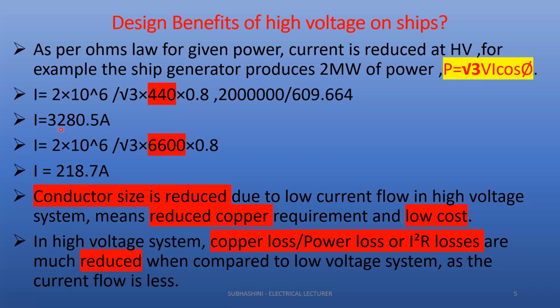So from 3300, the current value has come down to 220. So we can see the change. We can see the difference between 3300 and 220. So this many times the current is getting reduced since we raised the voltage from 440 to 6600. But the power is the same. The power we use here is 2 megawatts. Here also 2 megawatts, 2 into 10 to the power of 6. The power is the same. I am only stepping up the voltage, so the current is getting reduced.